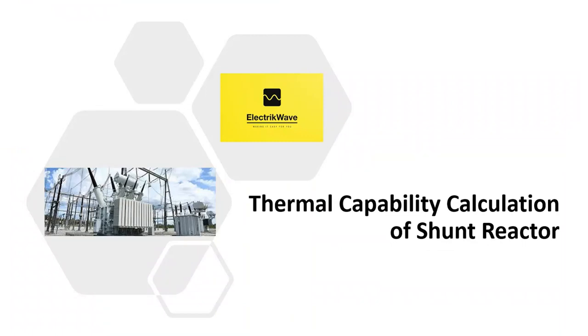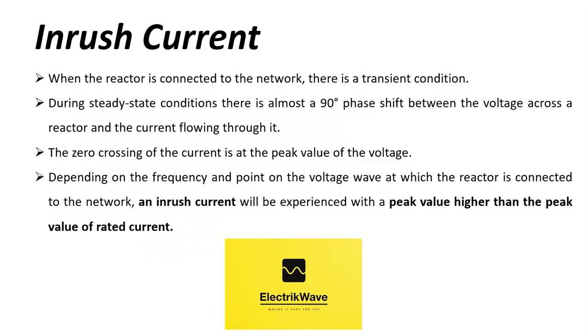Let's start with a discussion about the thermal capability calculation of shunt reactor. When the reactor is connected to the network, there is a transient condition. As mentioned in IEC, during steady state conditions, there is almost a 90 degrees phase shift between the voltage across a reactor and the current flowing through it. The zero crossing of the current is at the peak value of the voltage. Depending on the frequency and point on the voltage wave at which the reactor is connected to the network, an inrush current will be experienced with a peak value higher than the peak value of rated current.